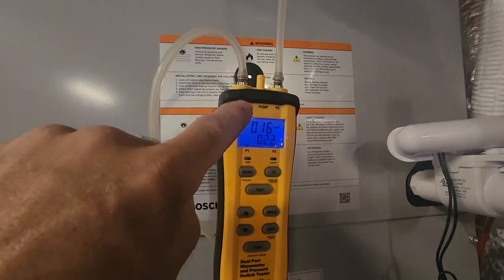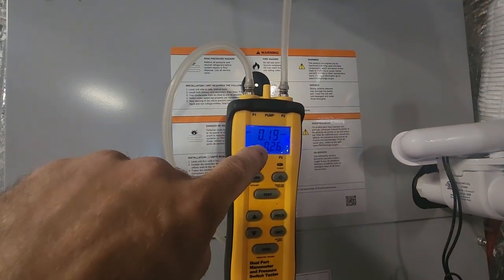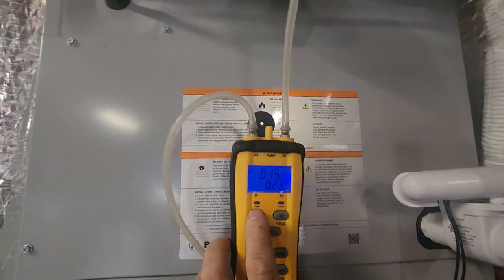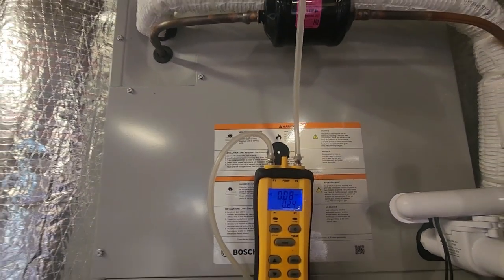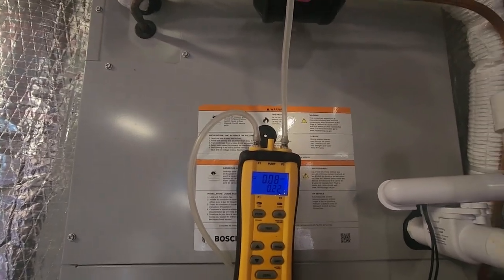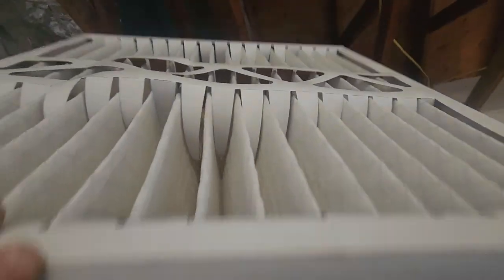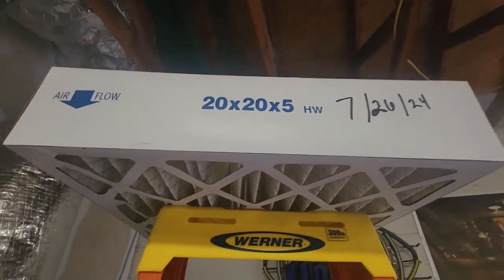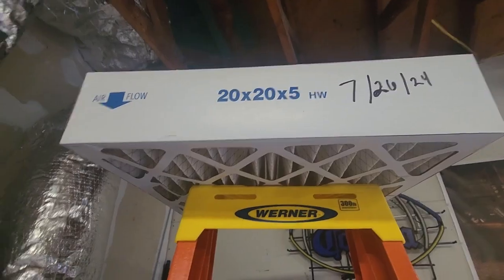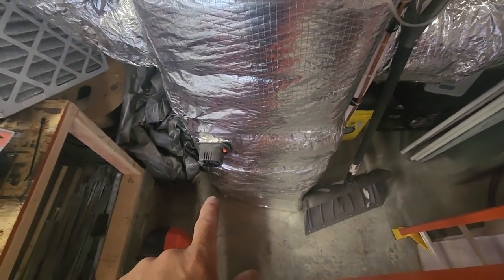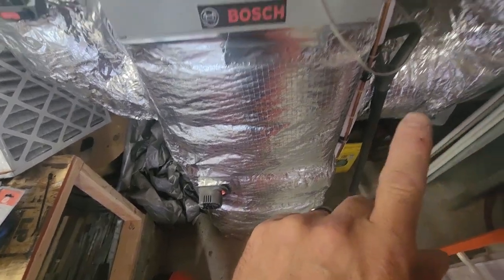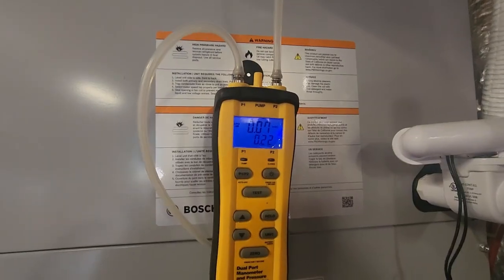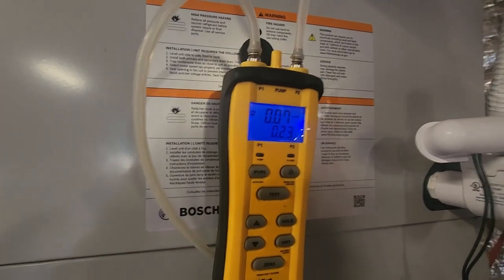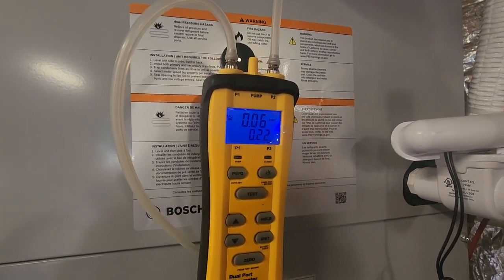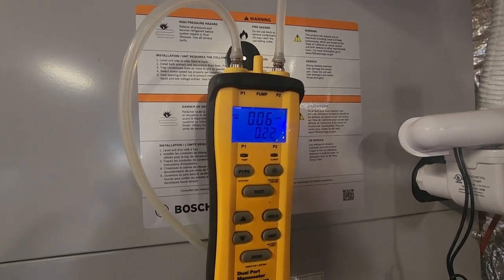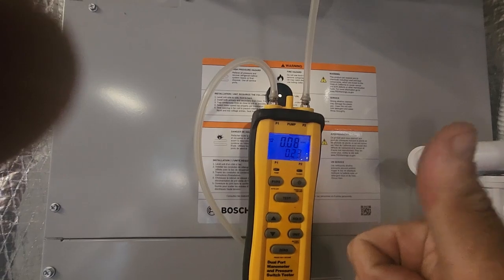Check that out. 0.16 on our supply, 0.17, 0.18, only 0.08. Let's pump that over. 0.08, 0.07 on our return. So that's awesome. That means these filters, so that's one I just put in the other day, and it's clean. It gives you less than 0.1 static on first stage. That is awesome. Right now we're still just running the downstairs. Let's flip them and see what we got without the filter in, with just the upstairs going. Okay, I have just the upstairs going now. So I guess these zones are ducted pretty similar static wise, as far as their total external static pressure. I give this a thumbs up.